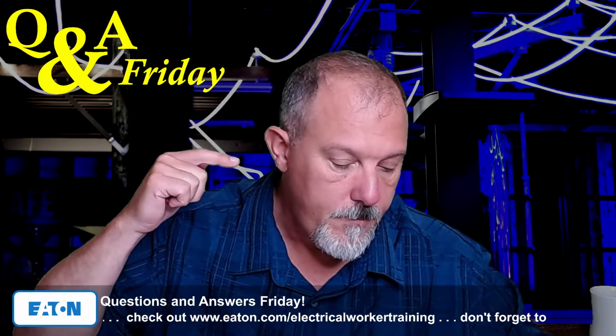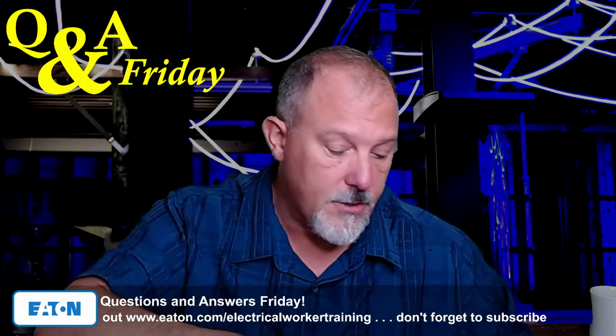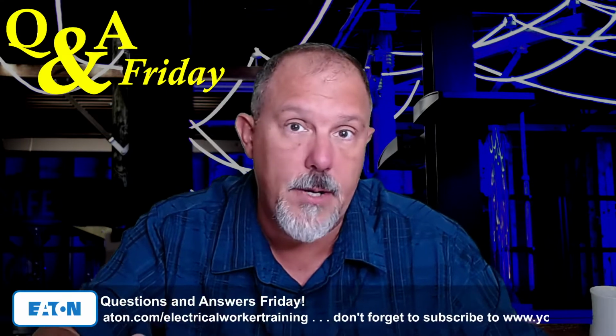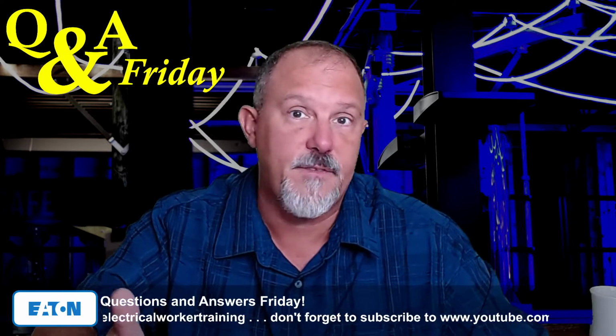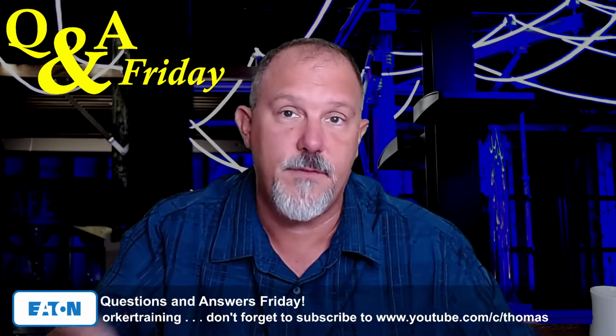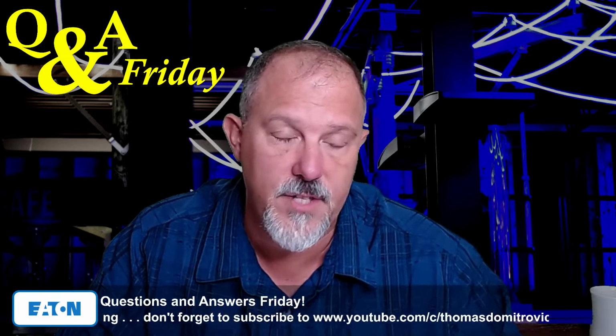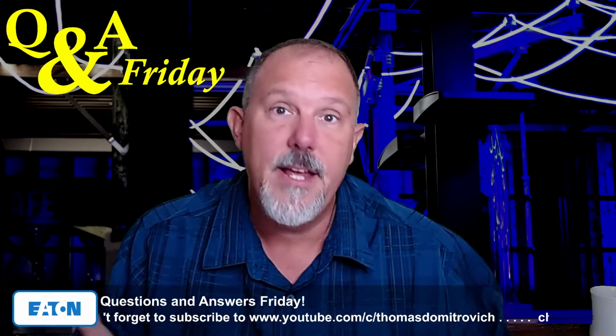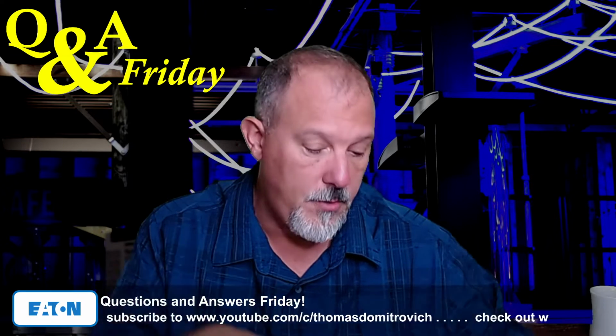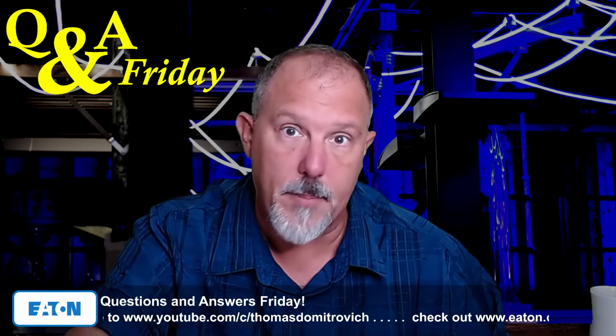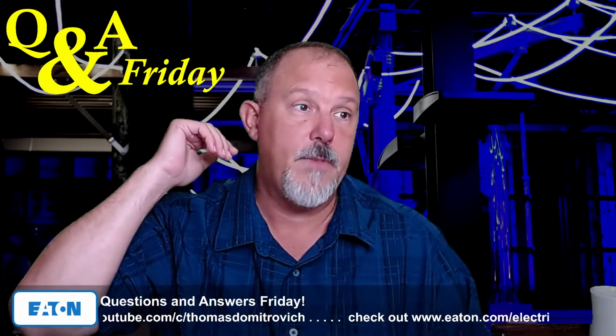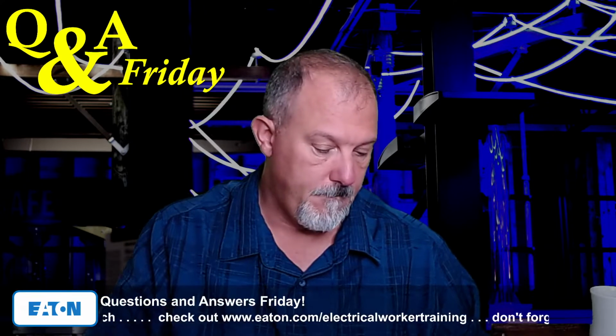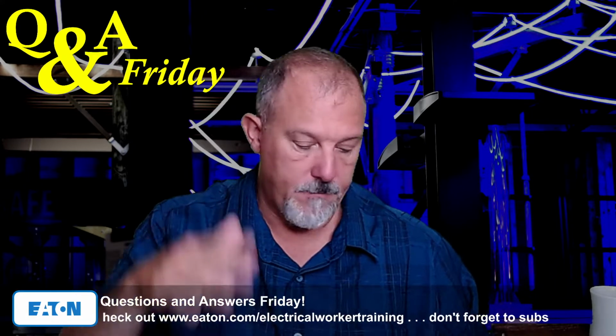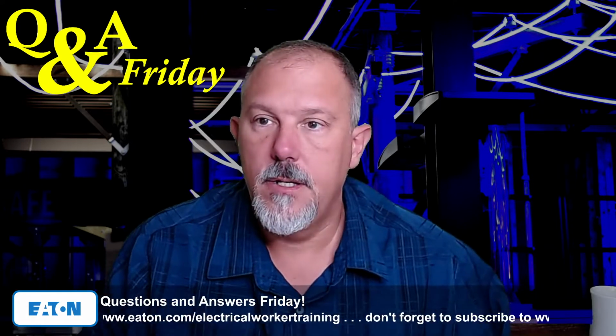And there's nothing else. So I don't care if it's a DC breaker, an AC breaker, I don't care if it's set for locked rotor amps, I don't care if it's set for inrush currents on transformers, I don't care how you set it. If it can be adjusted to 1200 amps, you need to have 240.87. It could be on a fire pump controller. It could be in a life safety system. There's no exceptions for 240.87. Yeah, no exceptions. I hope that helps, Al.